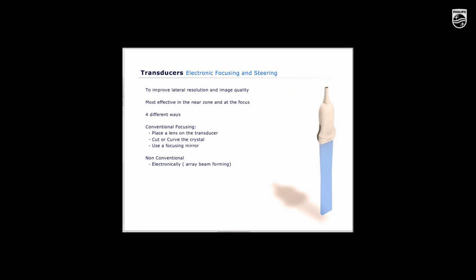The purpose of narrowing an ultrasound beam is to improve lateral resolution and image quality. It is most effective in the near zone and at the focus. Focusing can be accomplished in one of a few different ways. One, by placing a lens on the transducer, or by cutting or curving the crystal, or, for non-conventional focusing, by electronic or array beam forming, which we'll explain in the next slide.